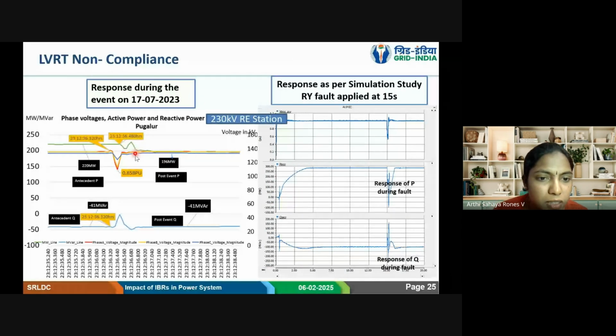In this case, we are seeing delayed response in the megawatt. The green color line indicates megawatt. Antecedent, the megawatt generated from the plant was 220 megawatt. This is also a wind plant, 220 megawatt. After the event, it is 196 megawatt. The event happened in the grid; it is not related to the RE. So for grid faults, the IBRs shouldn't have tripped. That we have observed.